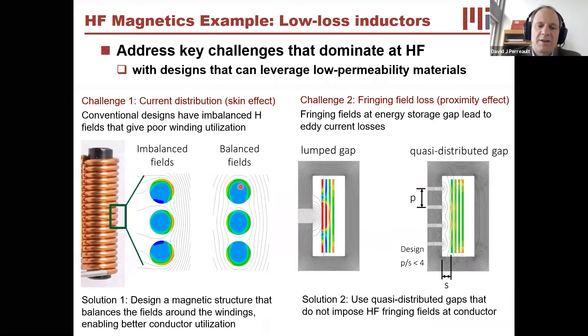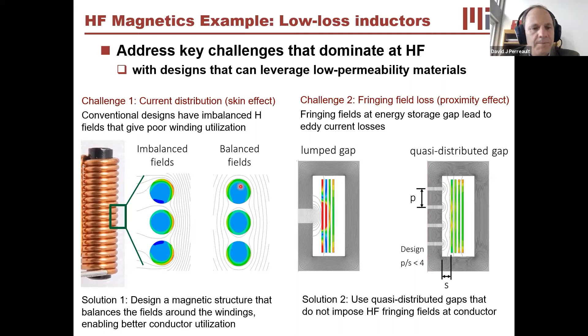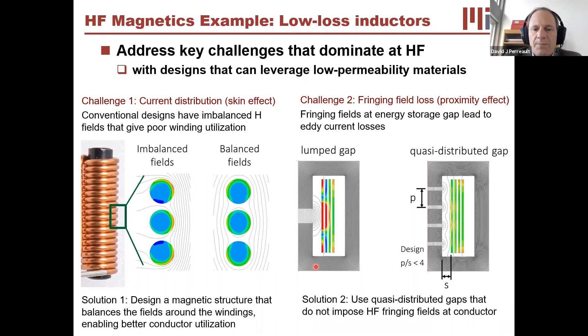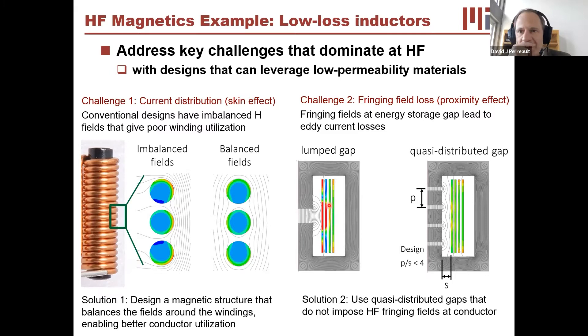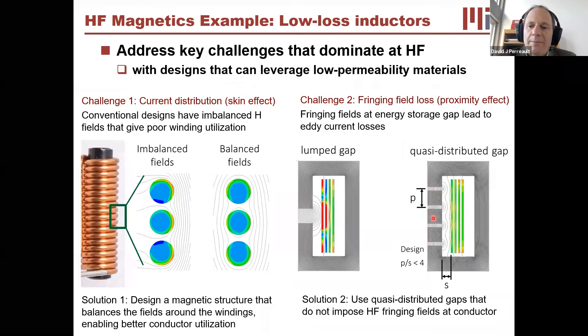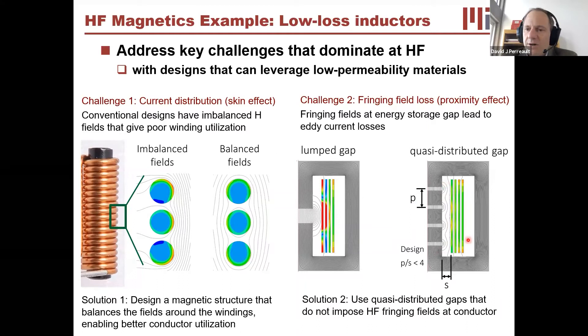If you can make the fields in the conductors very balanced, you can distribute the net current much more effectively across the conductor. Another limit is proximity effect from gap fringing: if you have a gap in the magnetic core to store energy, fringing from that gap hits the winding and induces loss. Those winding losses are extremely sensitive to frequency — often going up as frequency squared for a given conductor thickness — making high-frequency design very difficult. On the other hand, using distributed or quasi-distributed gaps can avoid large fringing and hence reduce proximity-effect loss in the conductors.